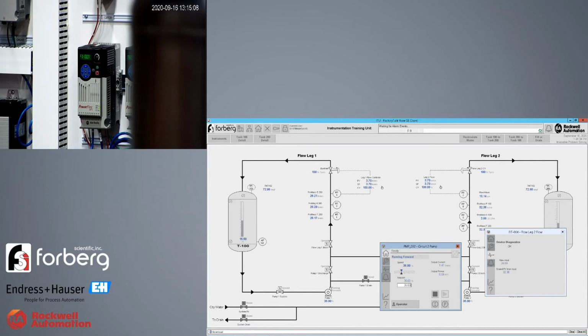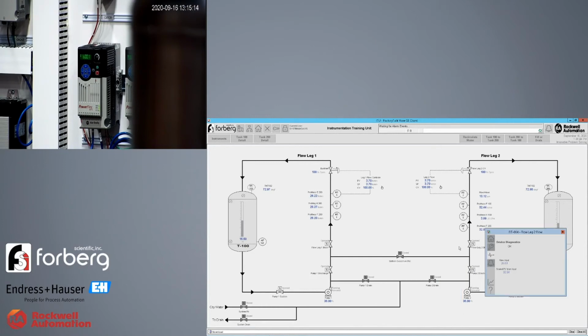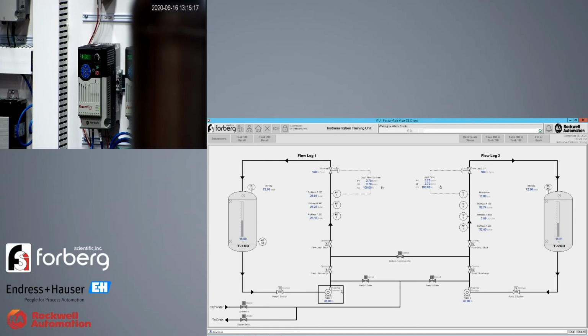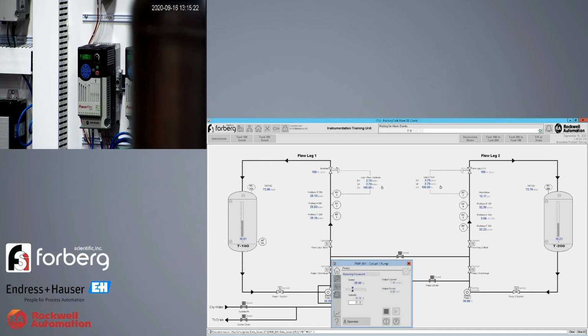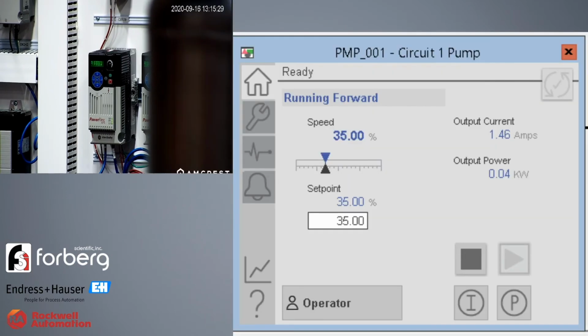Now I'm going to move from HART devices to EtherNet/IP devices as I open up our faceplate for pump number 1, which is a PowerFlex 525 drive connected directly to the control system via EtherNet/IP. On this process faceplate, you'll notice that the output current and the output power values are provided via Ethernet, again with no additional programming. Those values could be historized to capture energy usage based on this particular phase in the process, or to compare energy uses for a particular SKU made in production.